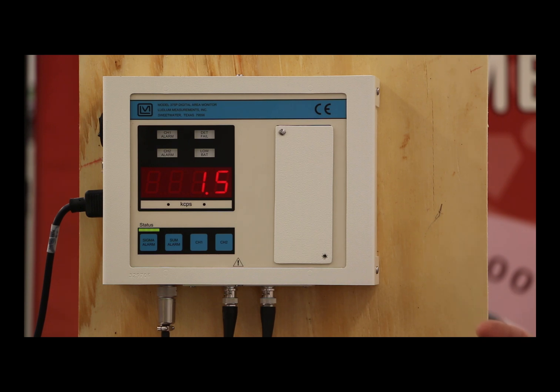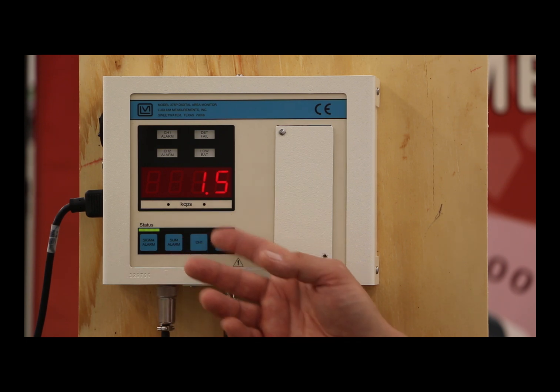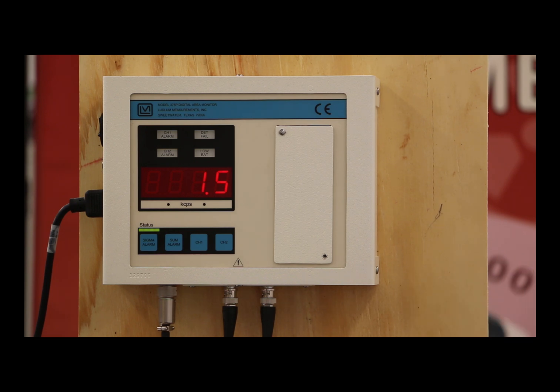The second alarm that we have is called the sigma alarm. Sigma is based on background. One sigma is the square root of the background. So right now, since we don't have sources around, really the square root of 1,500 counts per second would be equivalent to one sigma. That's going to be on the order of 25 or something along those lines.